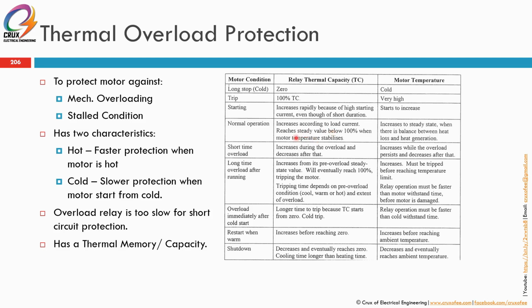Okay, so under normal condition, it should never reach the 100% TC or thermal capacity. For the motor temperature under normal operation, it increases to a steady state, when there is a balance between heat loss and the heat generated. For short time overload, thermal capacity will increase during the overload and decrease after that. And the motor temperature will also increase while the overload persists and decrease after that. So this is a comparison between thermal capacity and motor temperature.